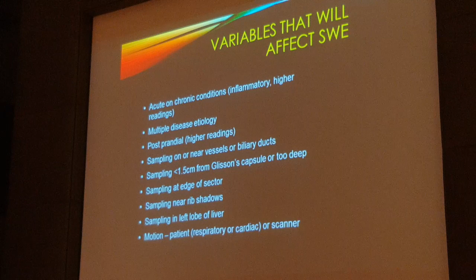Again, we don't want to sample near or on vessels or bile ducts. We don't want to sample within the first 1.5 centimeters from Glisson's capsule. And we don't want to sample at the edge of the sector. And again, we're using B-mode imaging, so you never want to take a measurement where there's shadowing, and you really want to try to get the best, strongest B-mode image, because that's telling you that you're getting in a lot of the energy and you're going to have better shear waves, so we would have more accurate measurements. Again, we're not going to sample the left lobe of the liver, and controlling both patient and scanner motion is very important.